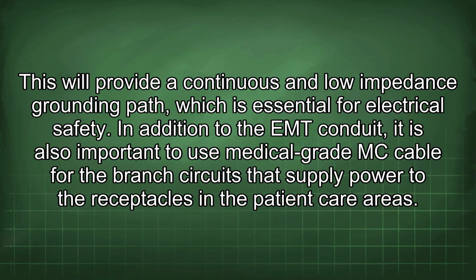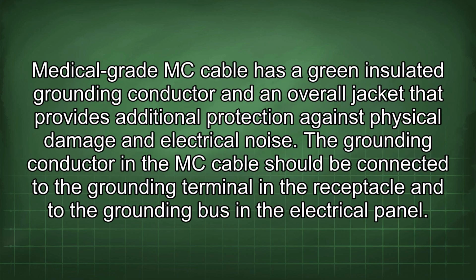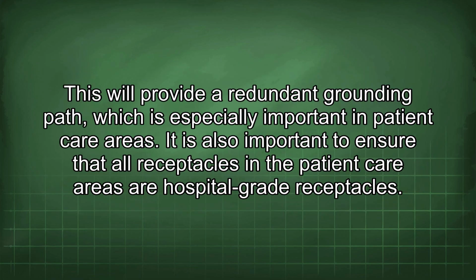In addition to the EMT conduit, it is also important to use medical-grade MC cable for the branch circuits that supply power to the receptacles in the patient care areas. Medical-grade MC cable has a green insulated grounding conductor and an overall jacket that provides additional protection against physical damage and electrical noise. The grounding conductor in the MC cable should be connected to the grounding terminal in the receptacle and to the grounding bus in the electrical panel. This will provide a redundant grounding path, which is especially important in patient care areas.